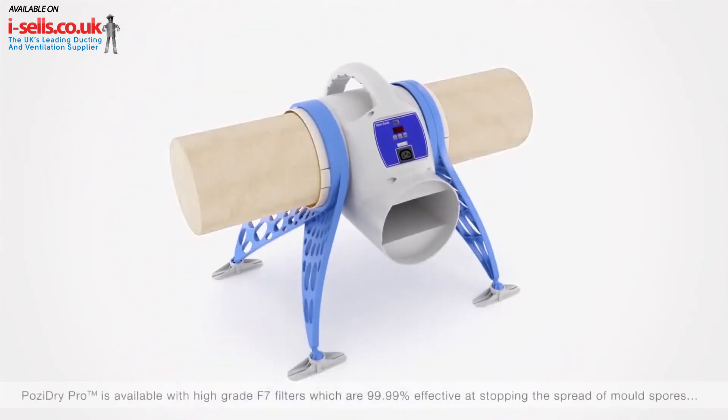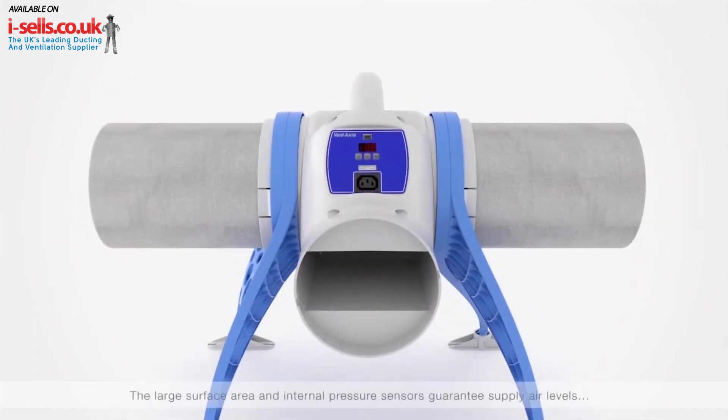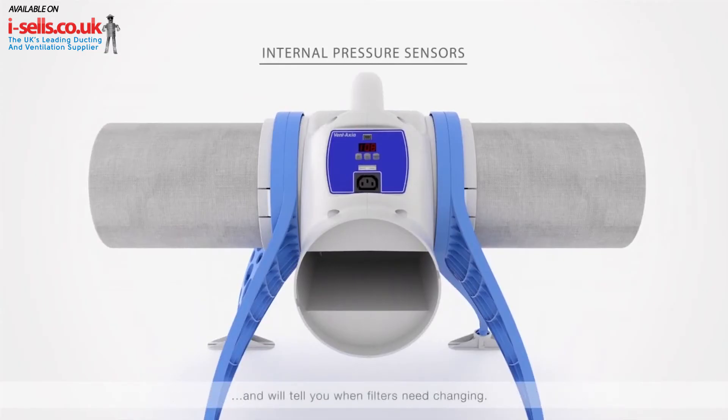PoziDry Pro is available with high-grade F7 filters, which are 99.99% effective at stopping the spread of mould spores and pollen, and capture particles down to PM2.5 including diesel particulates. The large surface area and internal pressure sensors guarantee supply air levels and will tell you when filters need changing.